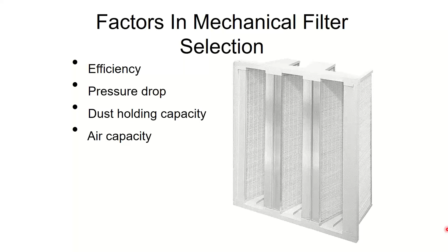When I select filters, there are many factors involved: the efficiency, or the ability of the filter to catch stuff, the pressure drop penalty through it. I don't want a very restrictive high pressure drop filter, and now I can't move airflow through the dang thing. That's not going to help me, right? And how much CFM I can shove through it as well.